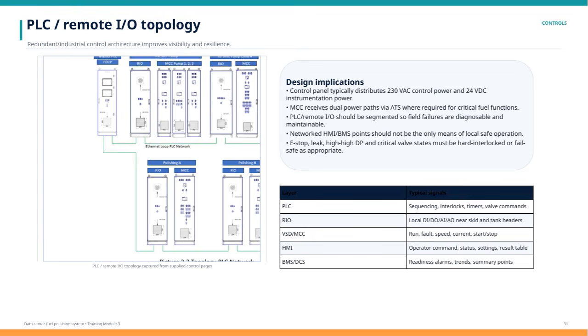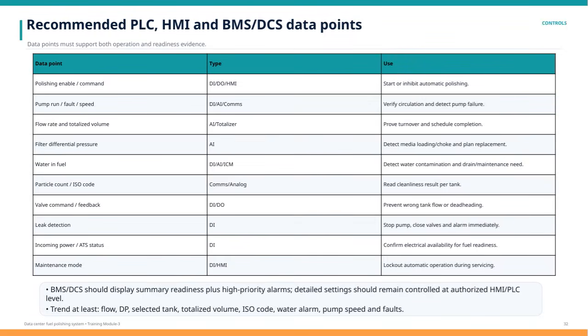Here, we focus on the critical data points recommended for PLC, HMI, and BMS or DCS systems in managing fuel polishing operations. These data points are essential not only for day-to-day operation, but also to provide evidence of readiness, ensuring the system is always prepared when needed. Under controls, we have specific points to monitor. For example, the polishing enable or command signals allow us to start or inhibit the automatic polishing process directly from digital inputs or outputs, including HMI commands.